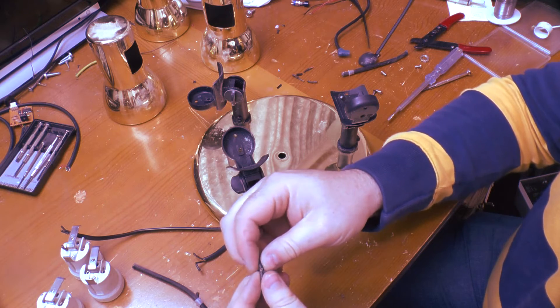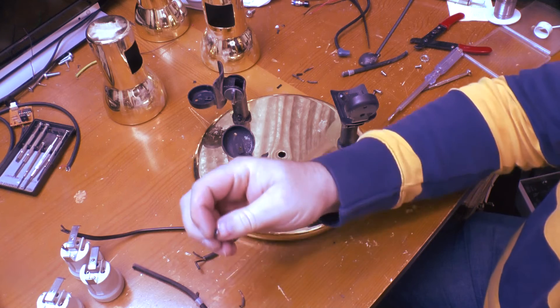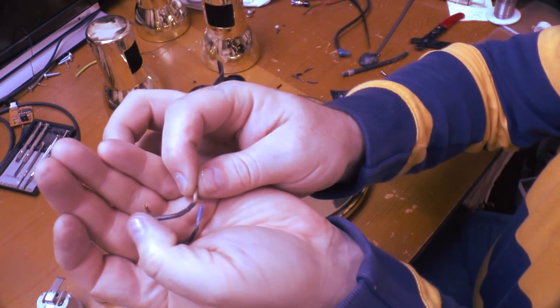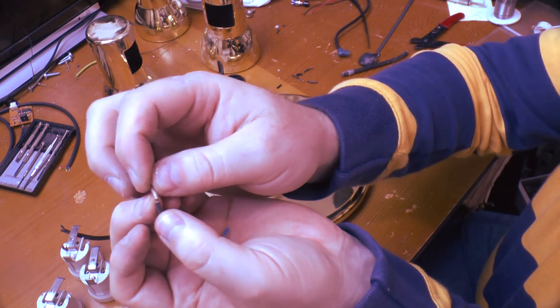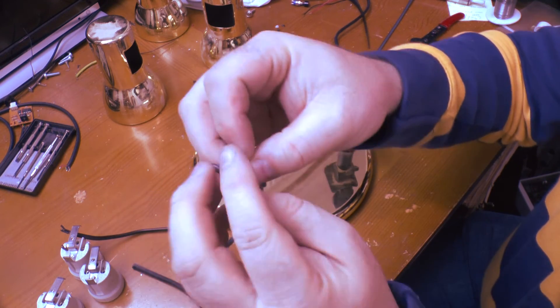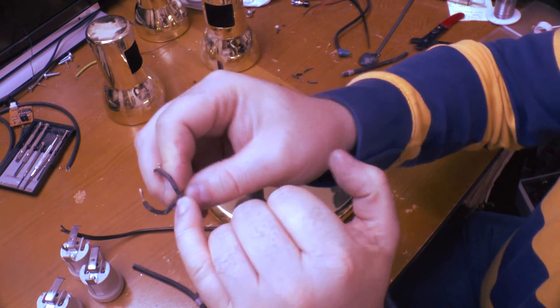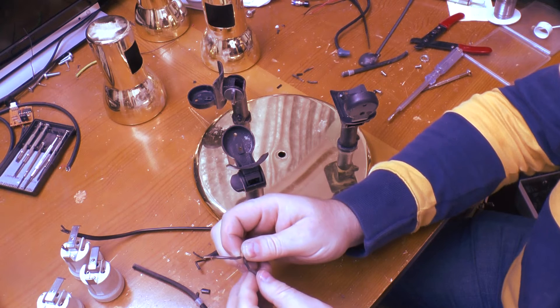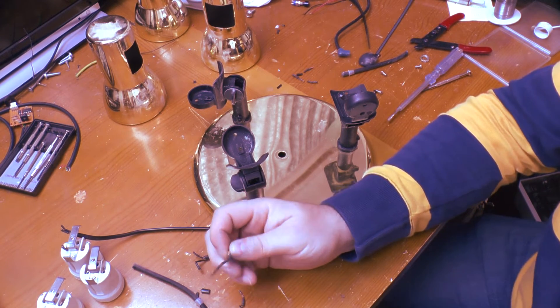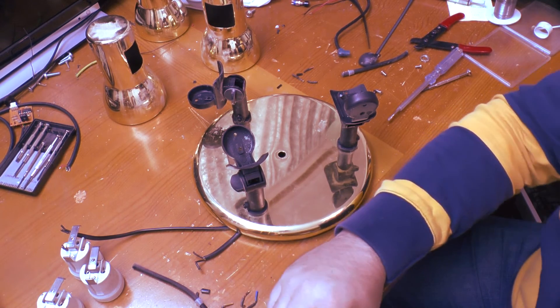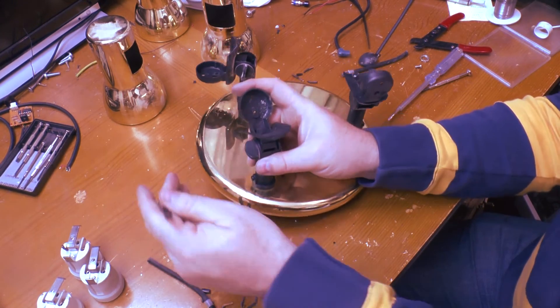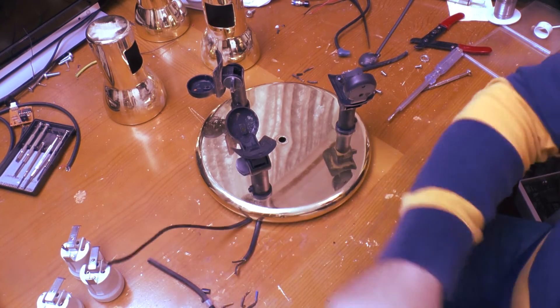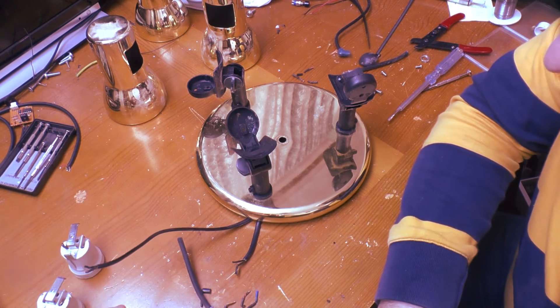Okay, here we are again. Let's take the insulation back there. Leaving us with heat shrink insulation over there which is split. Wires gone brittle there. Wires gone brittle there as well. So that is basically an arc across point. I'm not sure whether to actually replace this now. I've got a choice here. I can either overhaul it, replace these cables with something that's actually able to handle the temperature, some actual high temperature wire, and possibly replace one of these. I'm not sure. It depends if I can get the terminals out again.